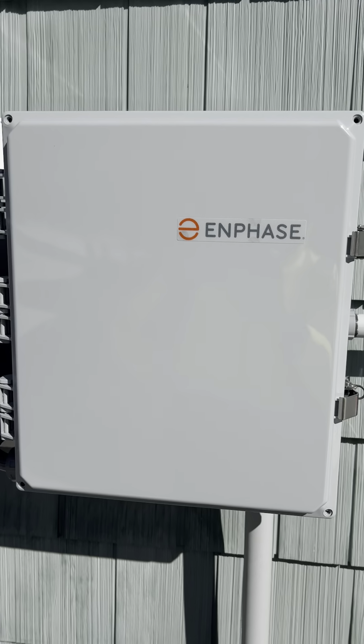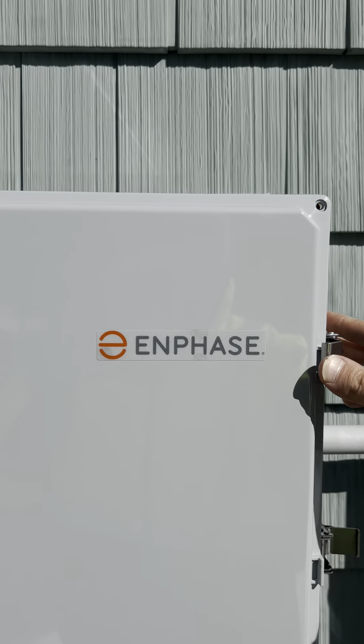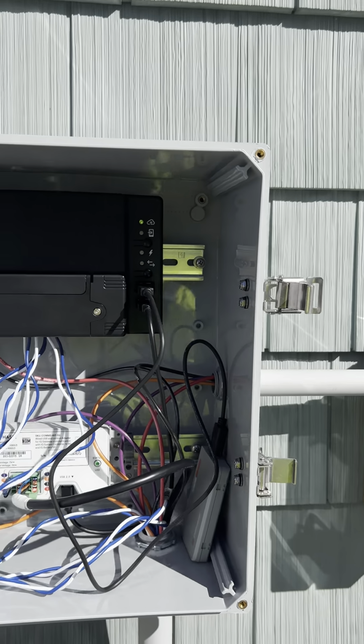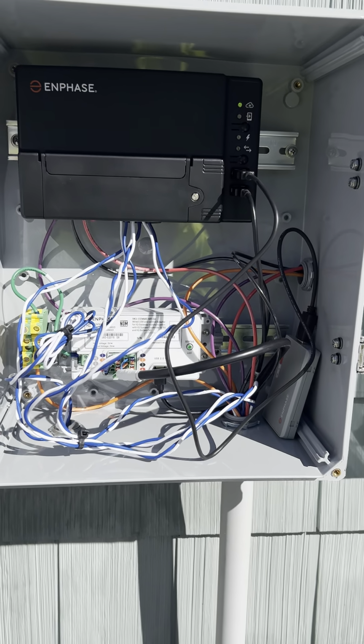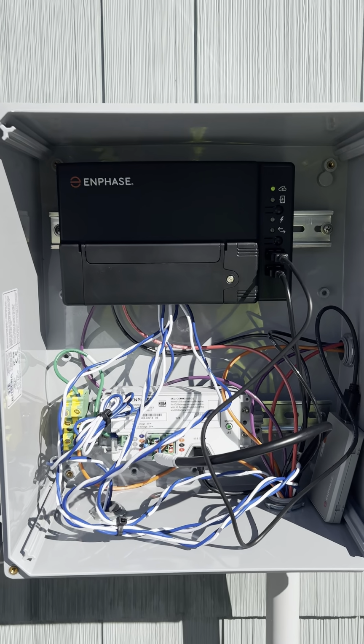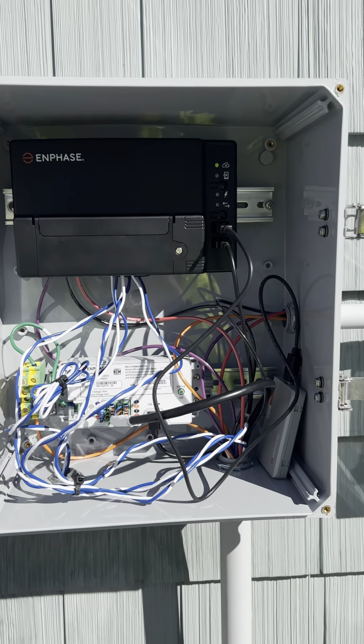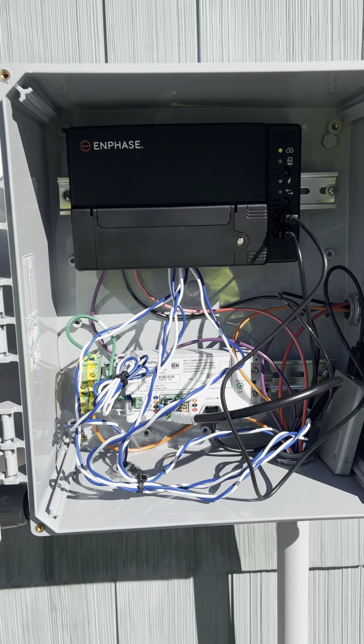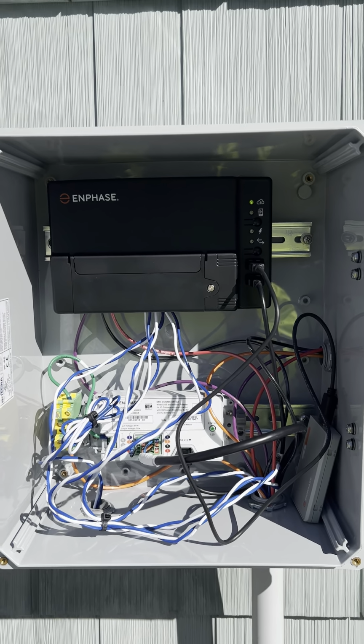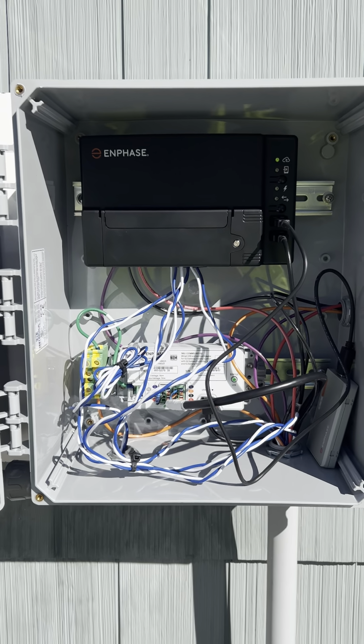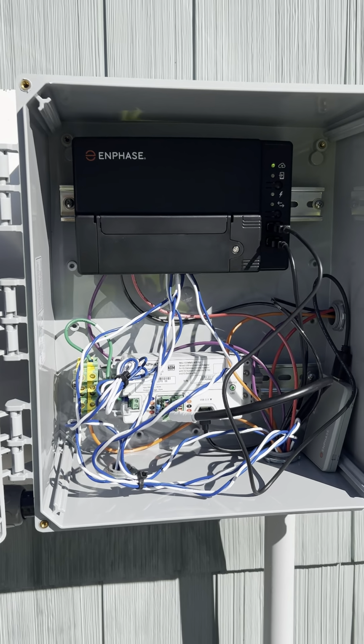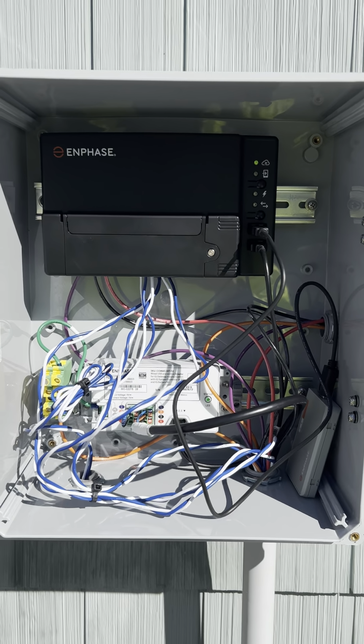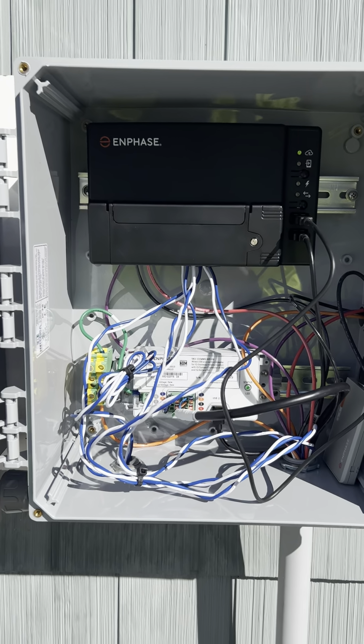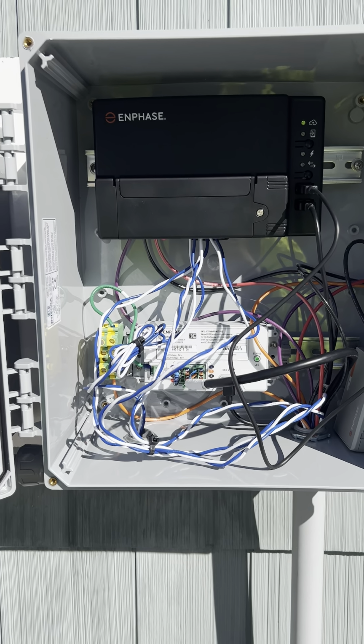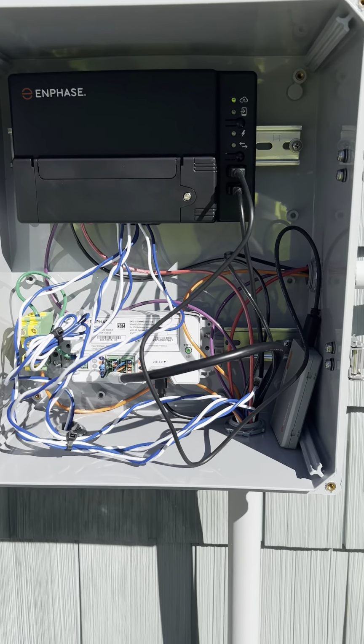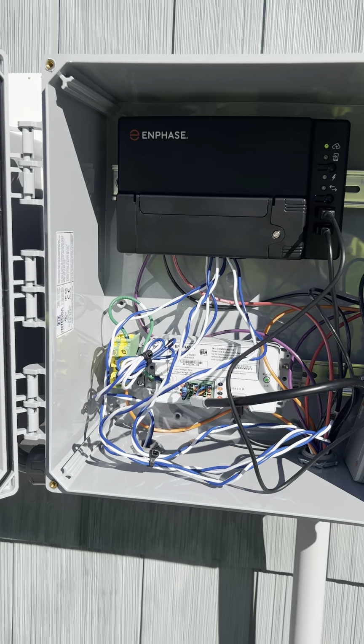Take a look here at our communication kit. This is where all our CTs here are being terminated. And we have our Envoy-S Metered. Envoy-S Metered is needed in this situation because, like I said, it uses the legacy M215 microinverters. And that one, the old communication used 120. Obviously, the new communications Envoys here use 240, and it supports obviously CT monitoring for both consumption and batteries, and of course the PV as well.